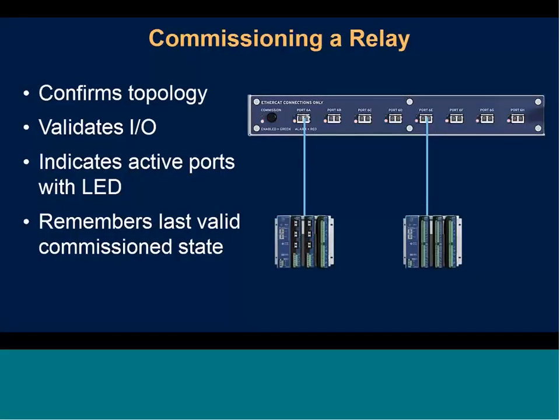So if we look at those connections there, we mentioned a few slides ago how TiDL is easy to commission and troubleshoot. One of the ways we do that is with this commissioning button on the left of the EtherCAT board you see there. Essentially, when we pull the relay out of a box and get it new, it will not talk to any of the Axion units. So what we can do is push that commissioning button. The relay is going to go out and talk to the Axions and figure out what it's connected to. And then if it is a valid topology, it will turn the LEDs green, indicating that everything is good to go. It will also indicate which ports are commissioned.